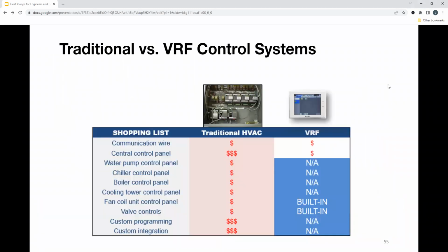So we're looking at traditional versus heat pump controls. As you can see, with VRF, all we need to do is add communication wire and a central control panel, right? That then and there is all you need to add on, and the system will run completely fine on its own. Whereas on the other side, with your traditional system, we're going to need a lot more controls and panels added on to control each one of these pieces of equipment. That just shows, from a heat pump side, there are rumors out there that VRF does come at a premium. However, people kind of leave out the fact that everything communication-wise is built in, and you don't need any really external controls added onto a project, whereas on a project like this, you will.